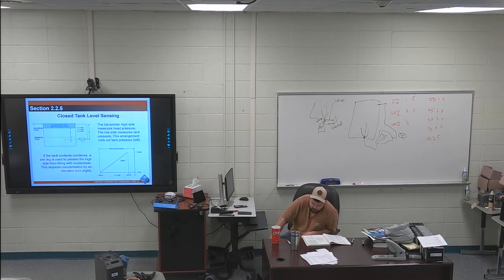My first highlights on the right-hand side of page 15, the first full paragraph, first two sentences. Low side transmitter piping in a closed pressurized vessel installation will remain empty as long as the gas above the liquid does not condense. This is referred to as dry leg installation, which is what I talked about earlier. I always should have waited for it.